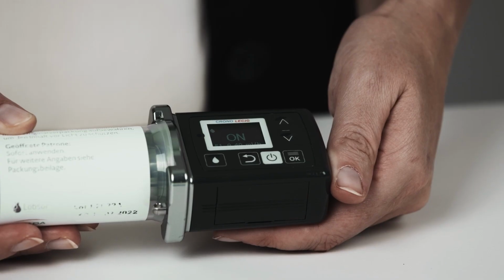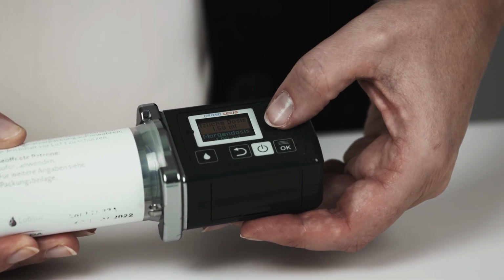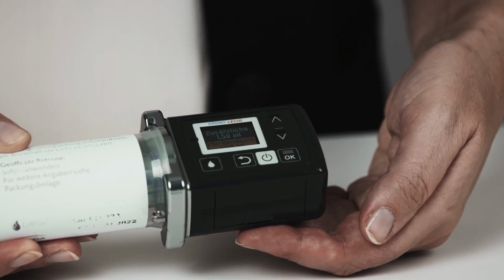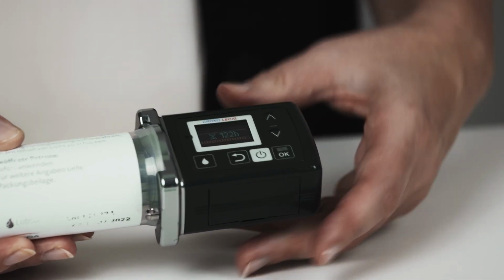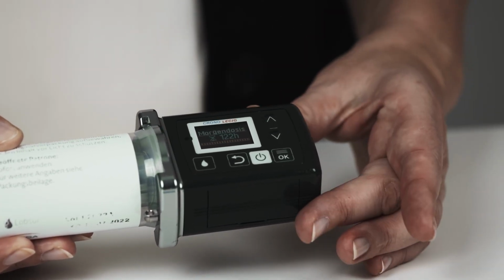Press and hold the droplet button. Use the down arrow key to select morning dose from the menu. Press and hold the droplet button. The pump will now deliver the morning dose. After the morning dose has been administered, the pump automatically switches to the continuous dose for the rest of the day. During the day, the patient can administer a bolus by pressing the droplet button. Put the pump in a carrying bag to wear it comfortably over the day. The pump can be worn for up to 16 hours.